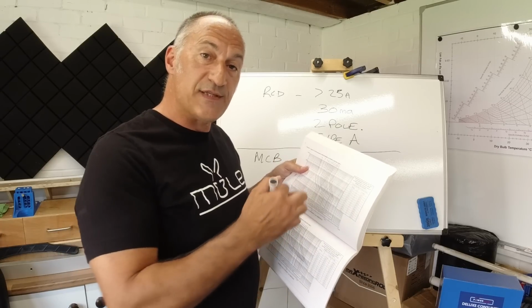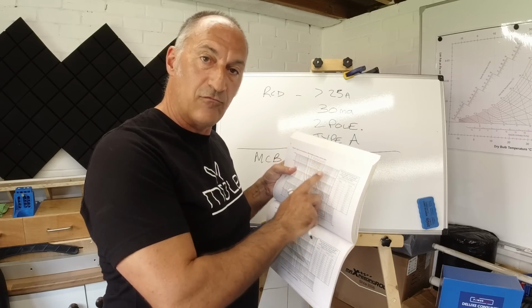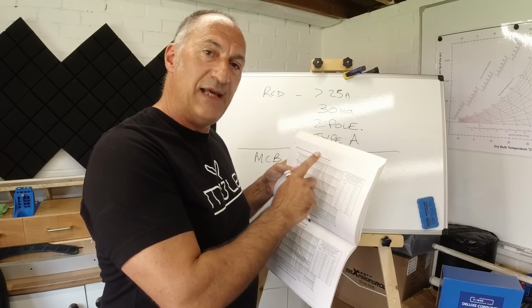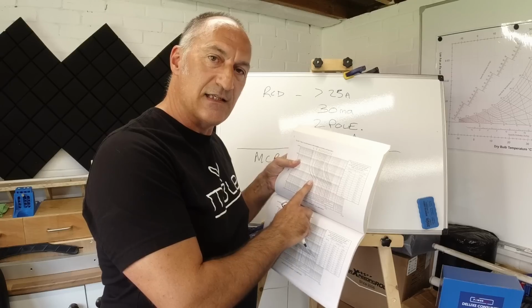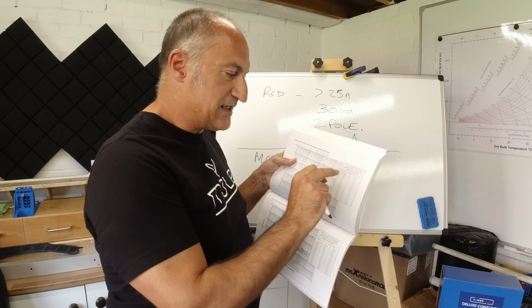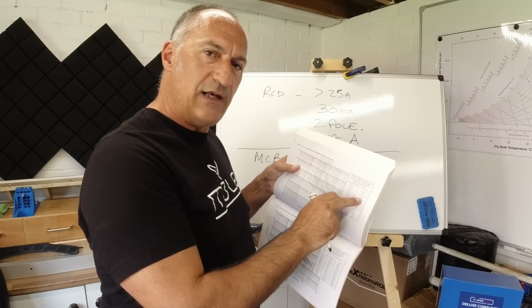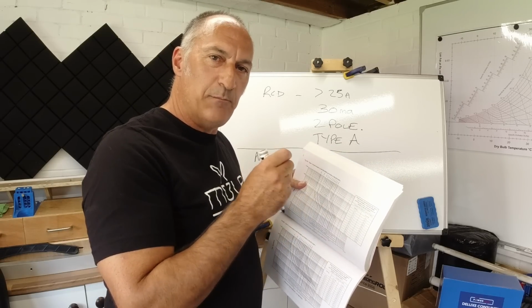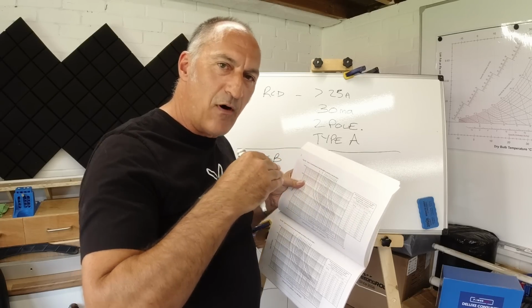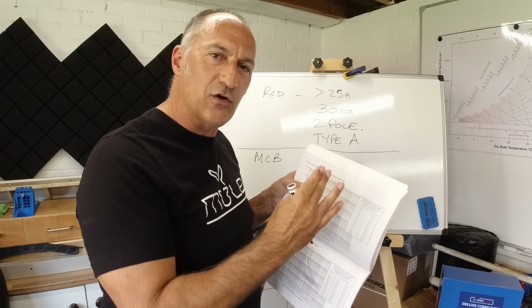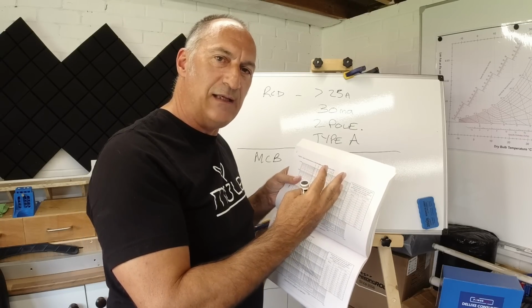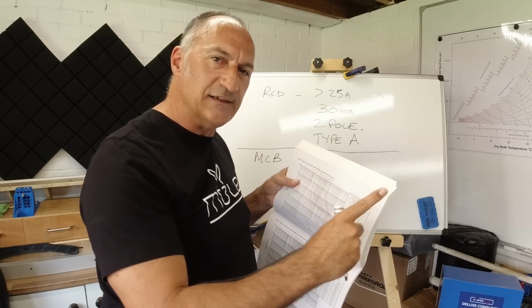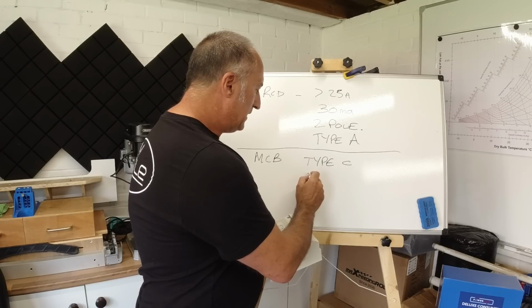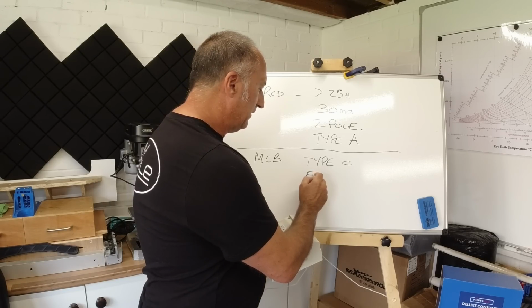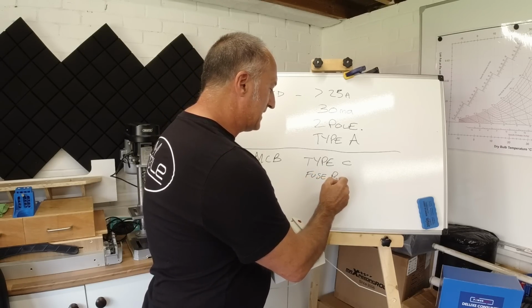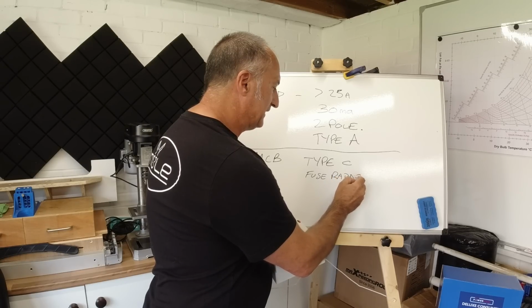So for a type C MCB rated at 10 amps, to make that MCB trip instantaneously, the short circuit current needs to be 100 amps. Anything below 100 amps, there's a very short amount of time for that bimetallic strip to heat up and break the contacts. Anything above 100 amps, that little solenoid's going to trip it instantly. So we need to look at effectively the fuse rating for our circuits.